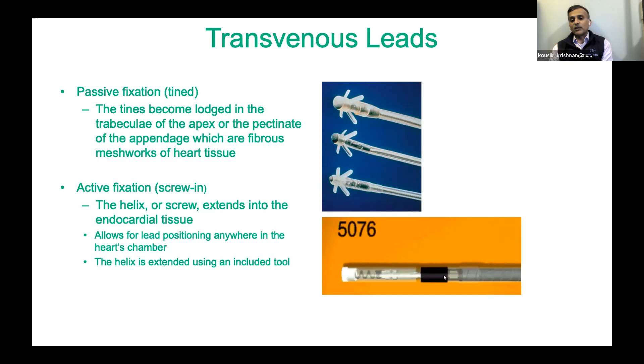So there are some advantages and disadvantages of each of these types of leads. When you're placing the lead, you have more options for locations with an active fixation lead because you can put it up against a smooth walled structure, because the fixation is a screw. Whereas the passive fixation mechanism is going to be a little more challenging if you don't have trabeculation to catch the tissue. In addition, when you're extracting these leads, if you're in an extraction center, if you talk to people that extract leads, active fixation leads are generally considered easier to extract, because sometimes when you unscrew the fixation mechanism, that may be enough to release it from the myocardium, or at least release a significant amount of it to where there's less force needed to remove the lead, and there's less of a fibrotic reaction at the end of the lead.